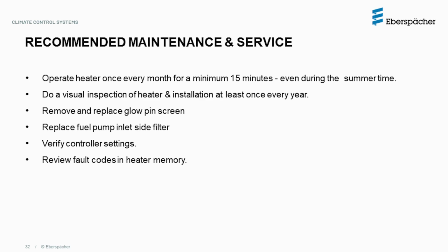It is recommended to replace the filter on the inlet side of the fuel metering pump on an annual basis. A choked fuel pump filter can affect the heater startup process and cause excessive smoke and failure to start conditions. It is also recommended to verify the controller settings every year before the heating season. Altered controller parameters may affect the heater operation. Finally, it is also recommended to review the fault codes in the heater memory and take proactive steps to fix the issues before the heating season begins.